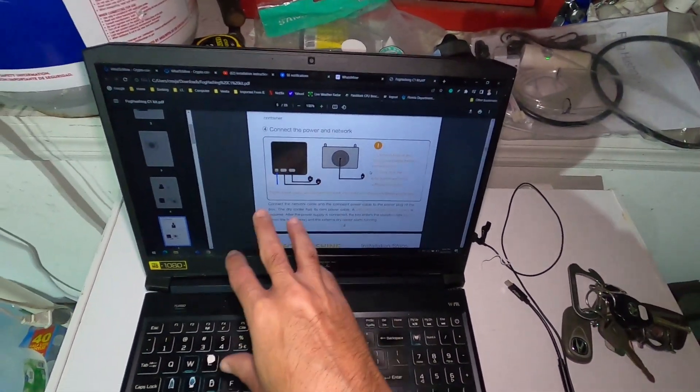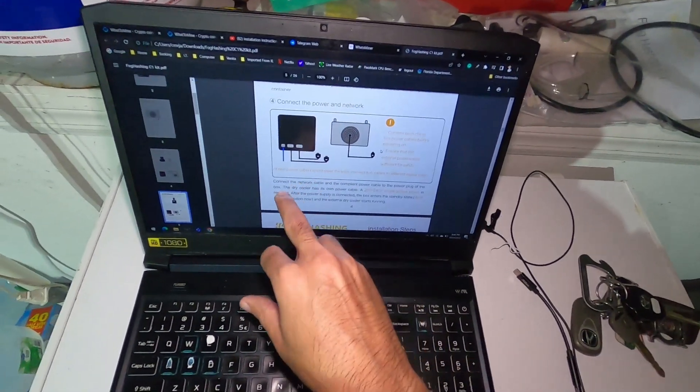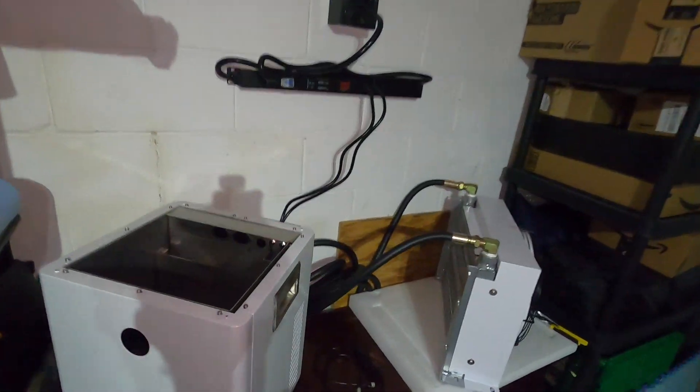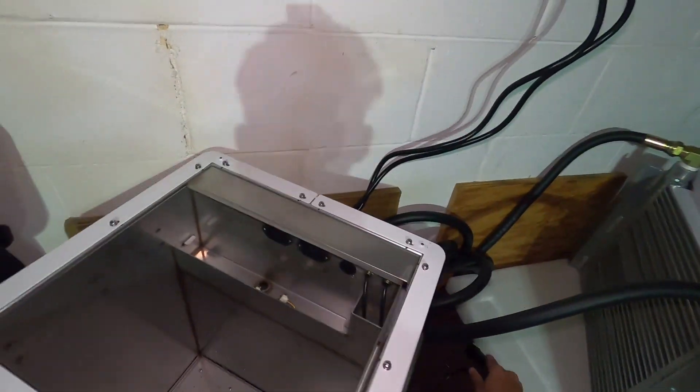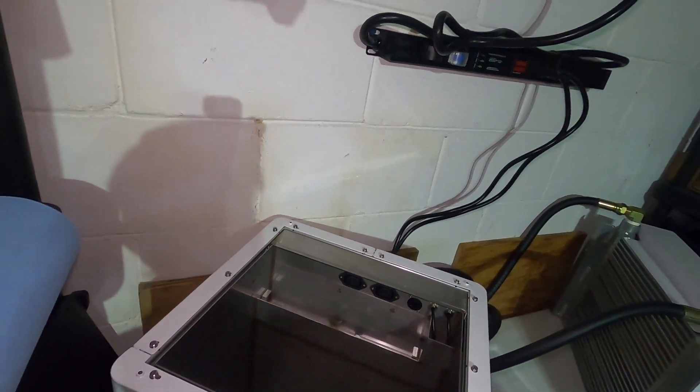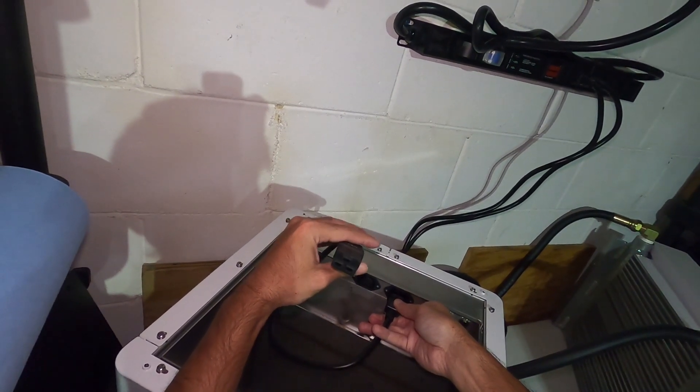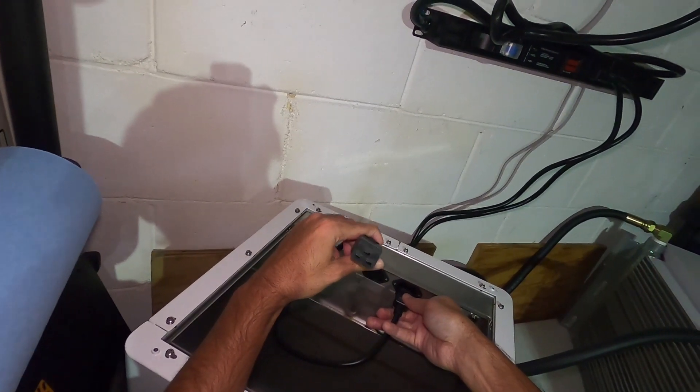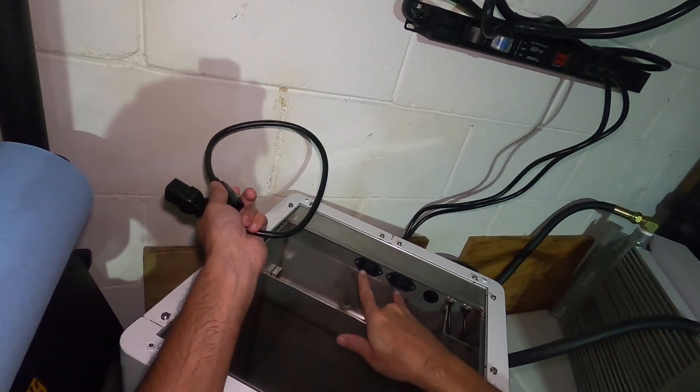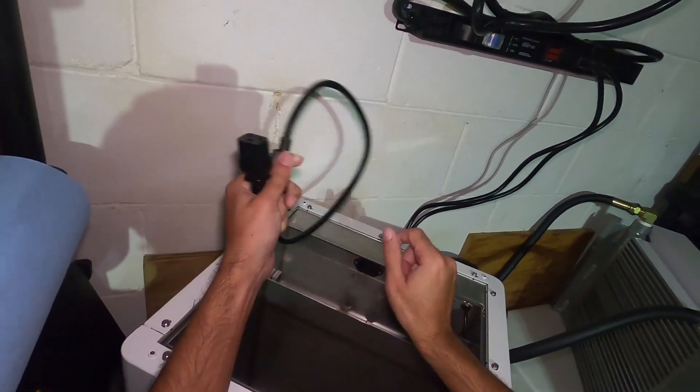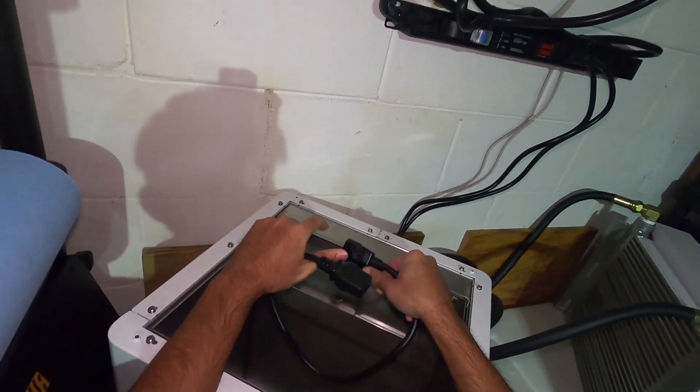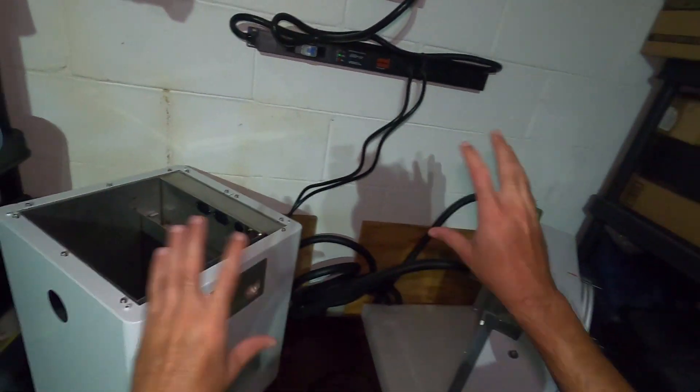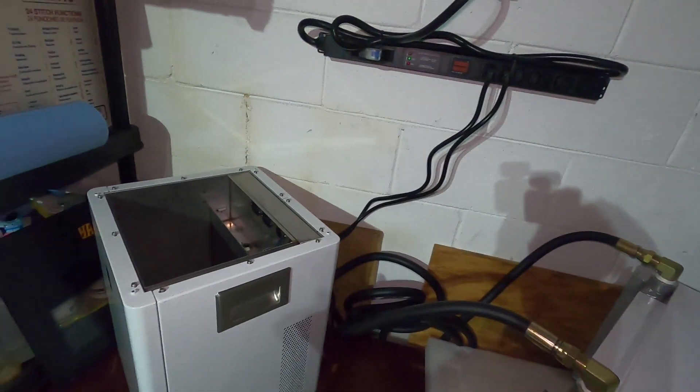Now obviously we need to connect our power cables. Bear in mind if one power cable cannot meet the load, connect two power cables on different power lines. My biggest problem is even though we got two cables going to the machine, because we're running an M30s it doesn't have a C13 to C14, it has a C19. Using this cable I'm only gonna be using one power port to provide all that power to the M30s, which is not recommended, not safe, and not my recommendation. What I'm waiting on is a dual power to one single C19. I wouldn't run this 24/7 just FYI.